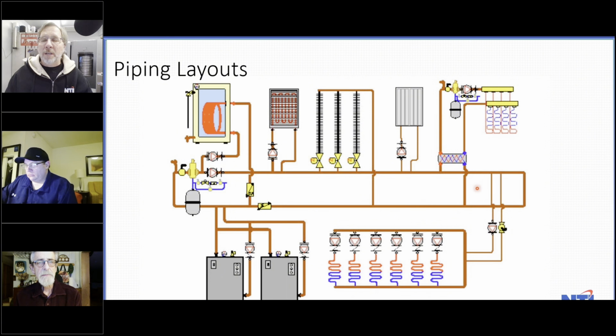I just wanted to point out too, Ted, that your return coming from the plate heat exchanger, which could be ice cold, is coming in after the two closely spaced T's for the radiant because you used the primary loop pump. You use this pump to supply the plate heat exchanger because you had the right head losses. You got the pressure loss across here because you put those T's so far apart, but you also took away the chance of these two T's getting colder water by being on the hotter side of the loop of the return, which I thought was excellent. Right. Yeah. That was the idea. Sort of. That definitely was the idea.